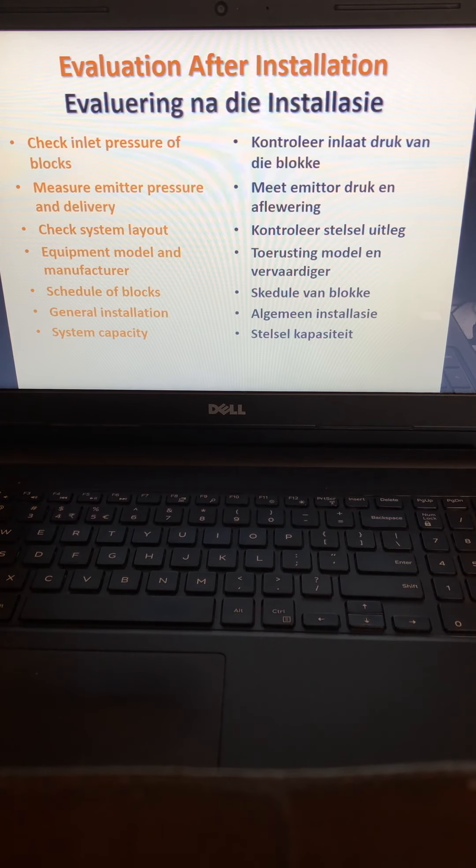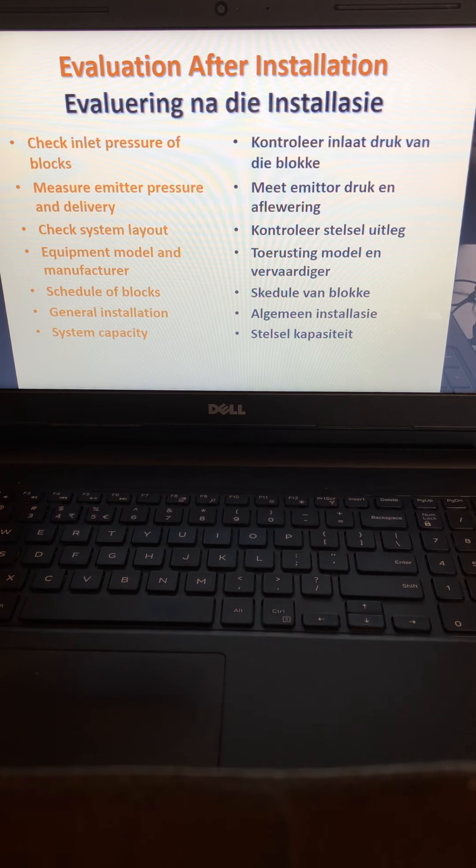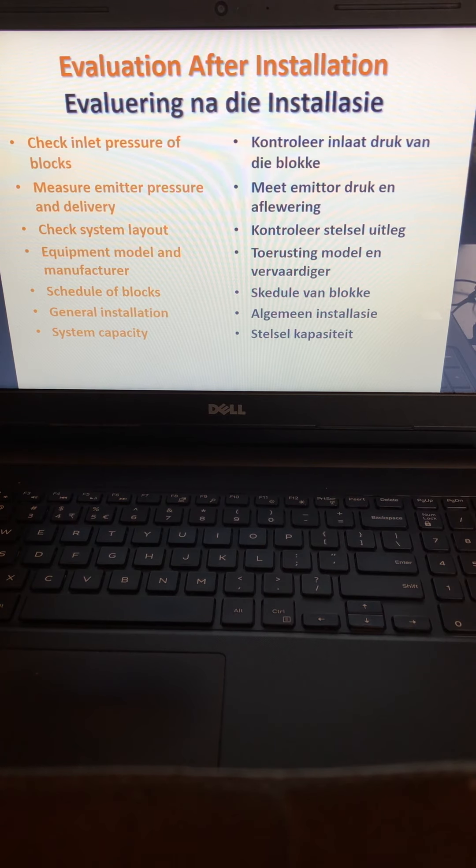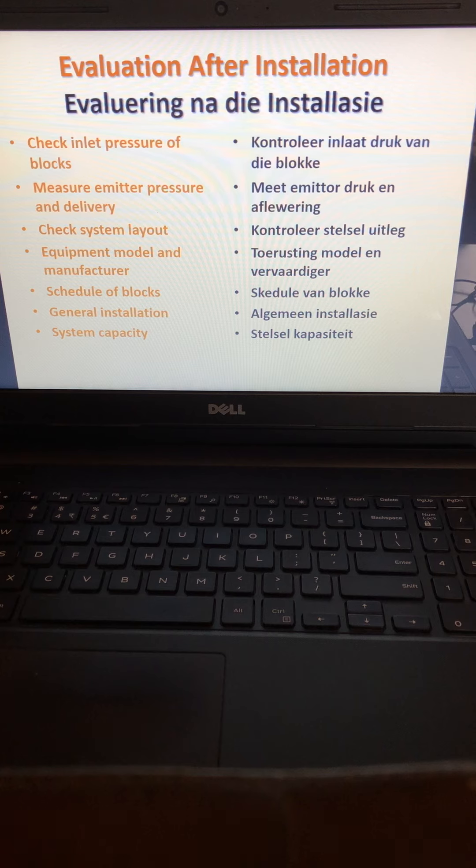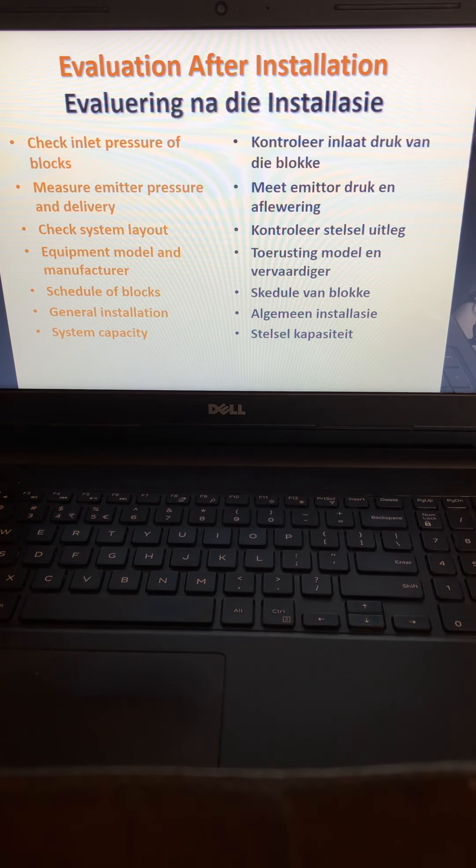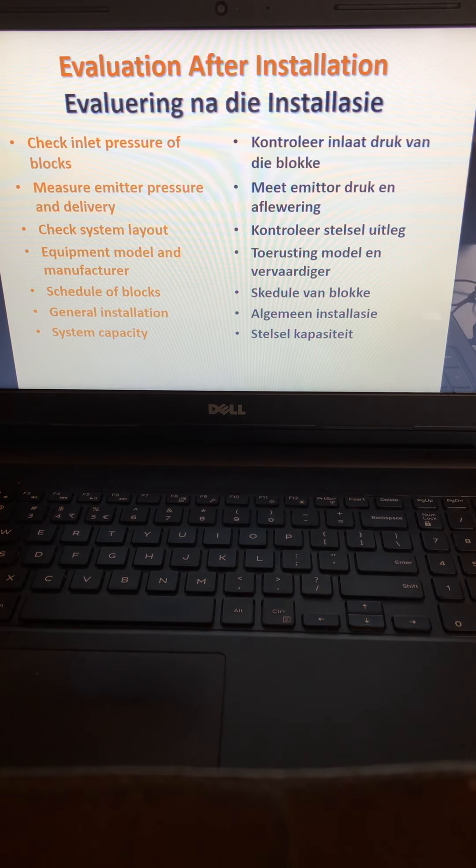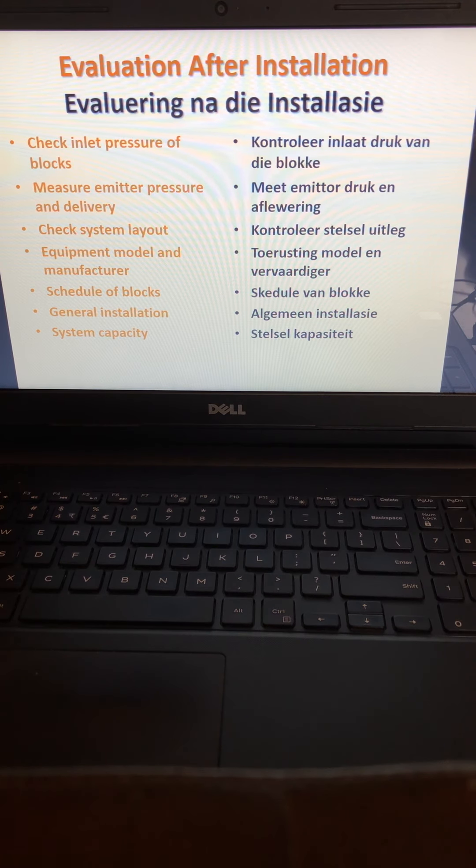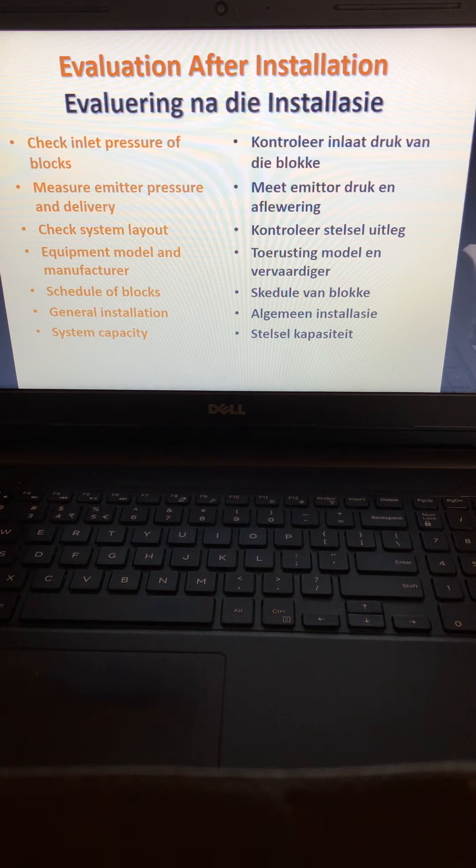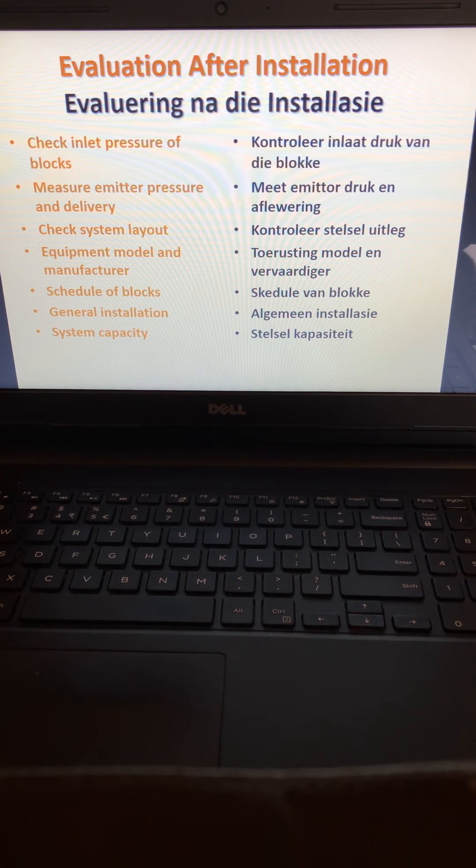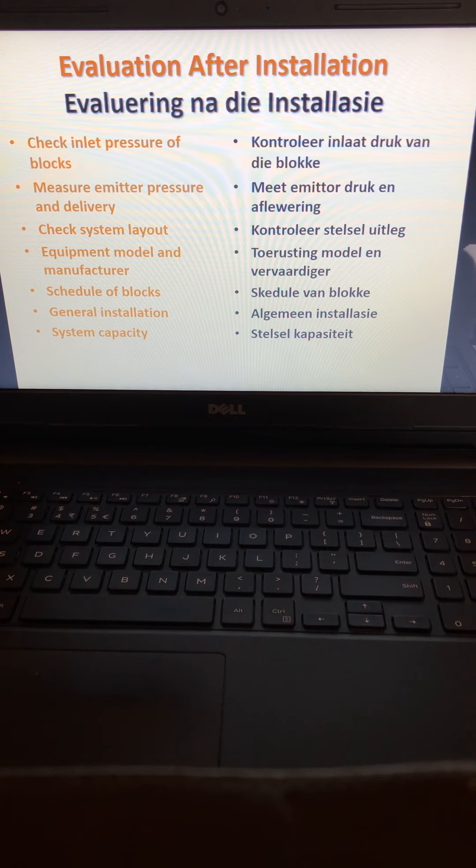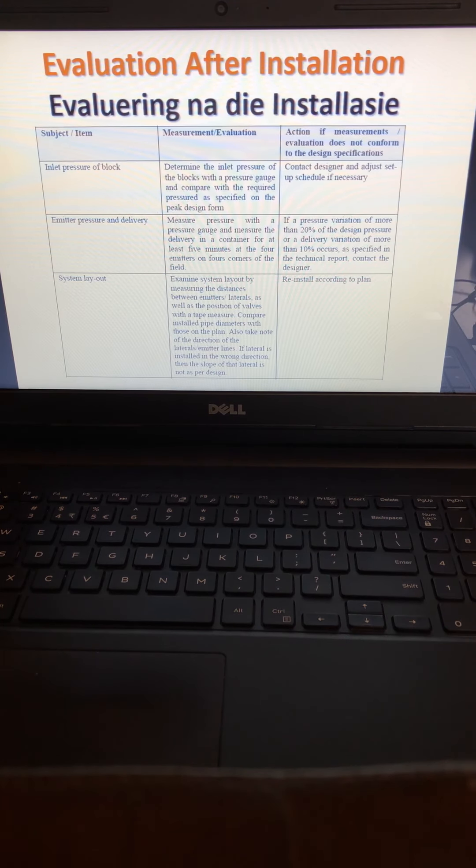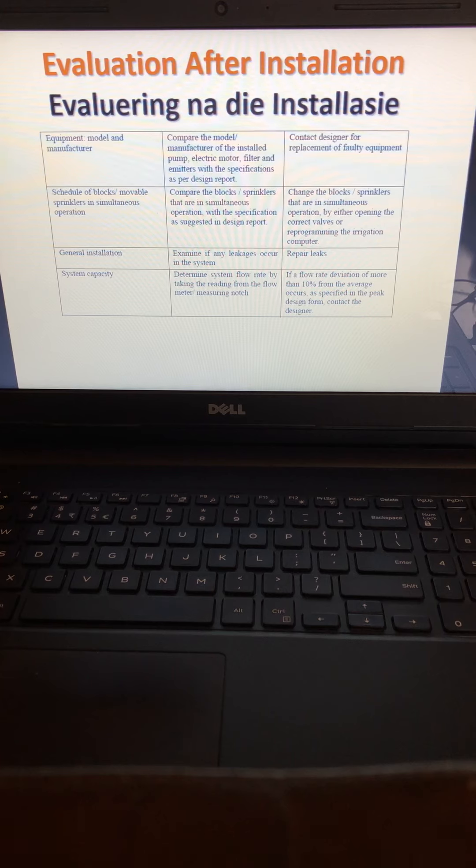Evaluation after installation includes checking a couple of places to see that everything is in order. Check the inlet pressure of the blocks, measure emitter pressure to make sure it's adequate, check system layout, equipment model and manufacturer, schedule of blocks, general installation, and system capacity.